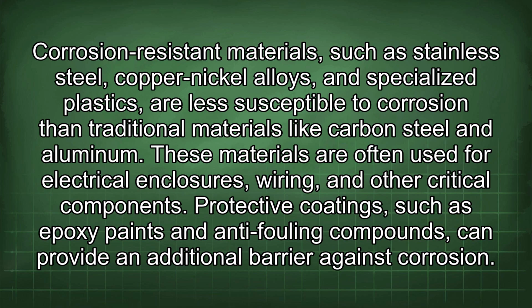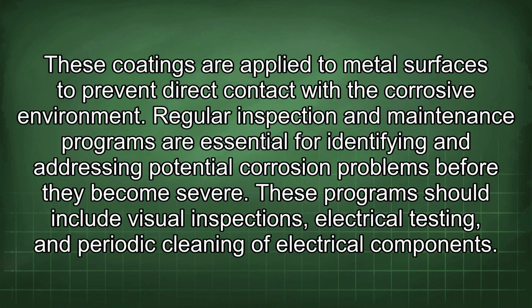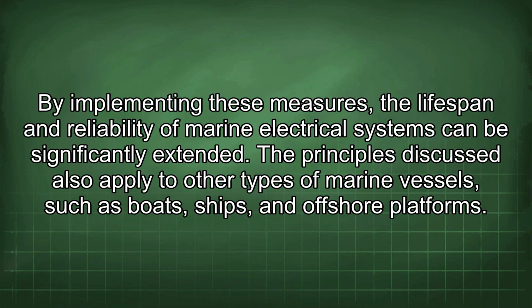Protective coatings such as epoxy paints and anti-fouling compounds can provide an additional barrier against corrosion. These coatings are applied to metal surfaces to prevent direct contact with the corrosive environment. Regular inspection and maintenance programs are essential for identifying and addressing potential corrosion problems before they become severe. These programs should include visual inspections, electrical testing, and periodic cleaning of electrical components. By implementing these measures, the lifespan and reliability of marine electrical systems can be significantly extended.